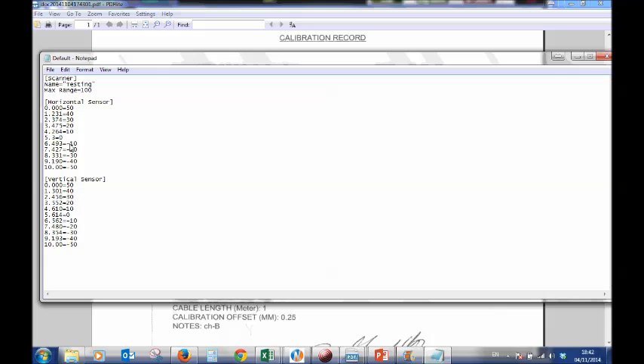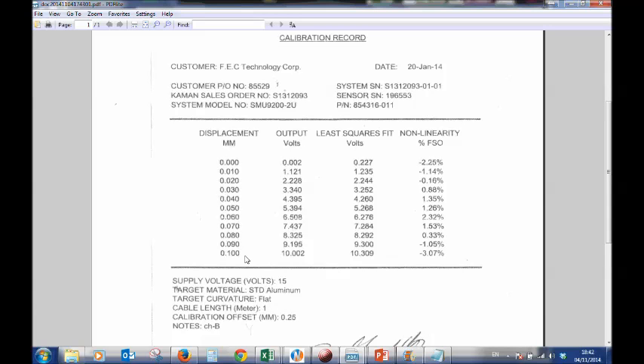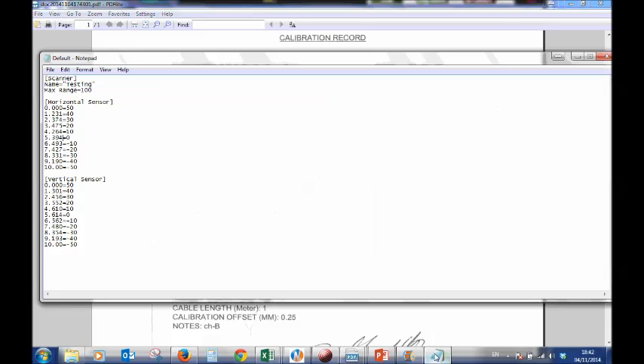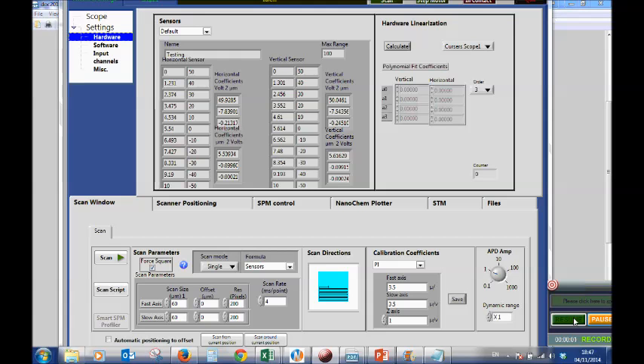And therefore here we put 5.394. And 10 microns up, okay, so that will be the 40. That's 4.395. So here we have to put in 4.395, and we fill out the entire calibration file for the horizontal and the vertical direction. Then we save it. After we save it, we can see it in the NWS software at the sensors, okay, the default. And we should also see the values here. It could be that we don't see them immediately. You just have to turn off the software and then turn it back on. You should see the correct calibration values in this table here.